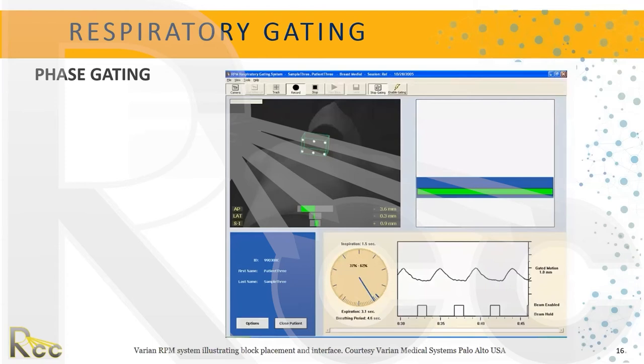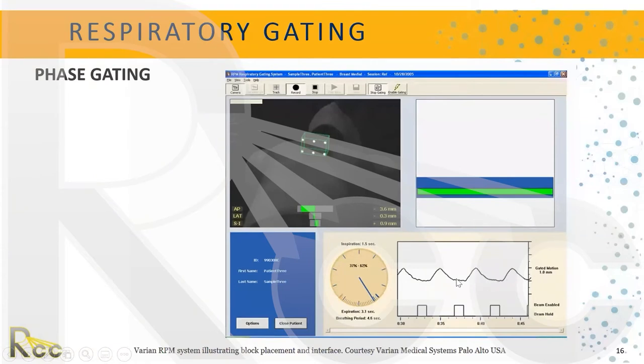The software shows the patient's breathing trace — inspiration, expiration — and displays how long each phase takes. For example, a patient might take about one and a half seconds to inhale and three seconds to exhale, so they're a bit longer in expiration. A box in the software controls when the beam is on and when it's off, helping turn the beam on and off based on the respiratory signal.